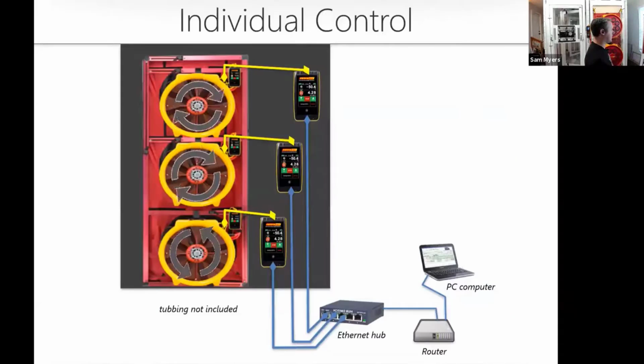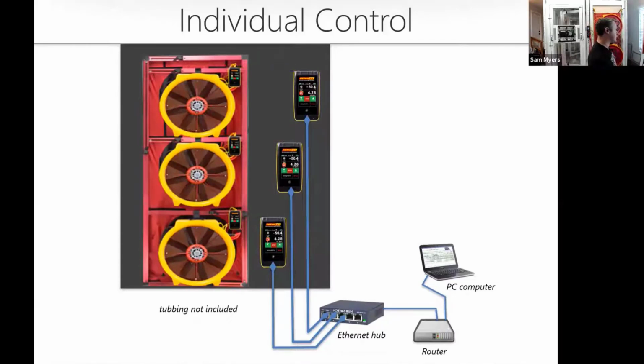With individual control, you can get fans spinning at different rates. If you use that equipment, one thing we recommend is looking at the motors with a thermal camera. If a few fans are one temperature and another fan motor is really hot, that one's likely spinning at a different speed and maybe getting pulled in a different direction. That's why we overcame that and did our common control method.